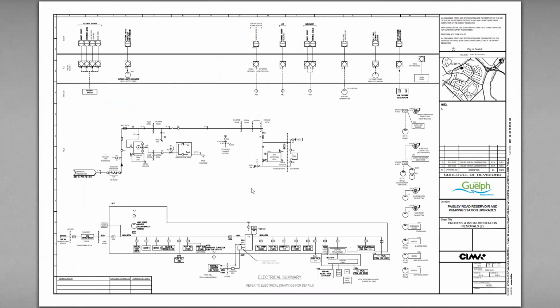We're going to then put new pumps in their place after rebuilding their pump mounts. Then we're going to commission those pumps. Then we're going to turn off the other set of old pumps. We're going to put new pumps in, wire them all to the old MCC. Then we're going to move over some other systems, and then we're going to decommission the old MCC and rip it out and decommission the old PLC. So it's a huge project.